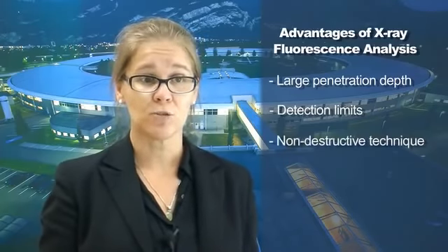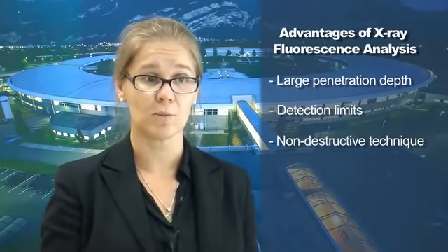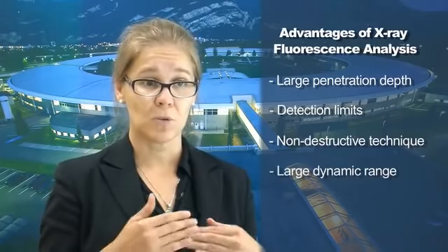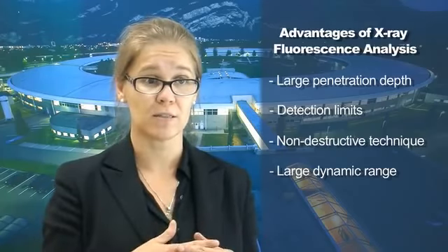X-ray fluorescence analysis, compared to electron or particle-induced techniques, has plenty of advantages. One of them is the large penetration depth, which gives more than surface sensitivity. A second one is the detection limits that can reach ppb levels. It is non-destructive, we don't need to section the sample, so you can bring it here as grown. In general, we have a large dynamic range. When I say that we go from ppb to 100%, we can cover the full range of intensities.